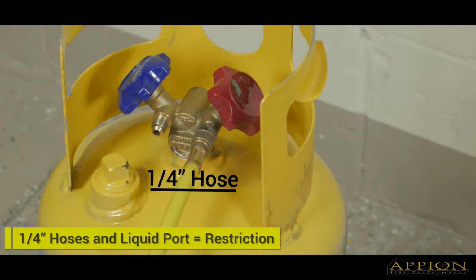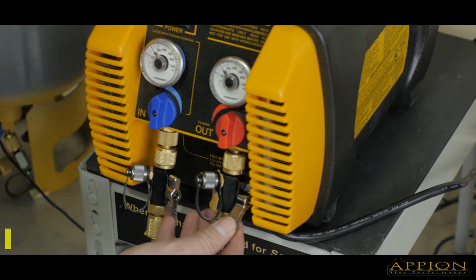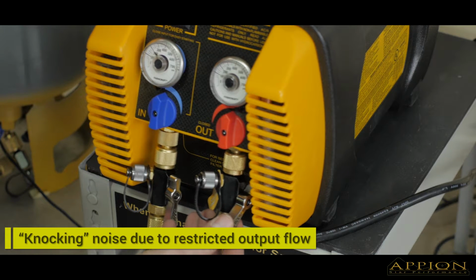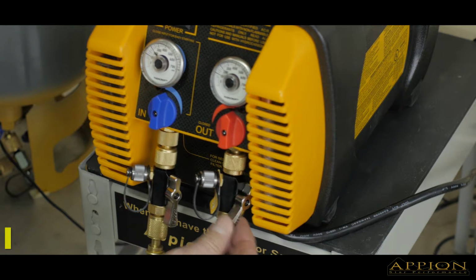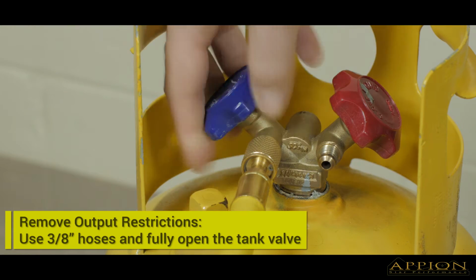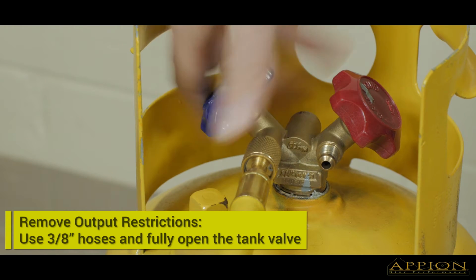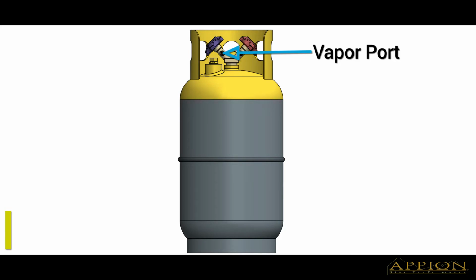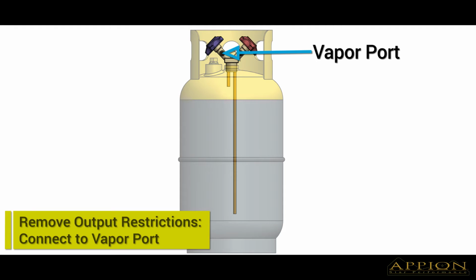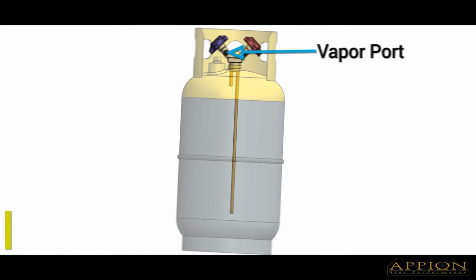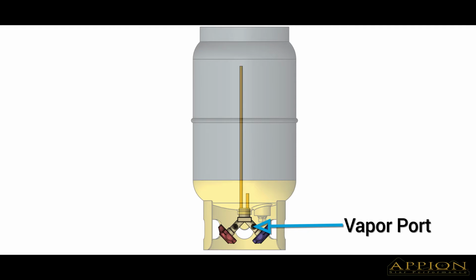Output restrictions are typically easier to diagnose. Knocking during liquid recovery occurs when the recovery machine is pumping refrigerant faster than the output line empties into the tank. Use 3/8 hoses to reduce the back pressure on the recovery machine and connect to the vapor port of the cylinder to avoid the restrictive liquid tube. You can rotate the cylinder during the liquid phase of recovery to fill from the bottom up, which in turn improves heat dissipation from the cylinder.